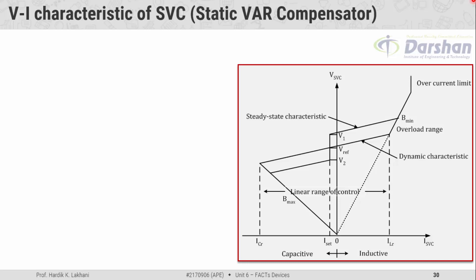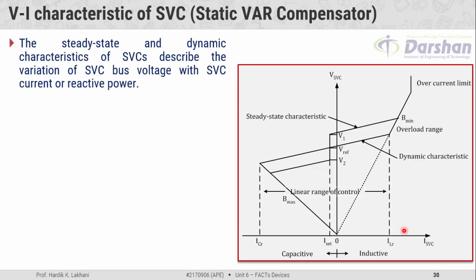This is the VI characteristic of the volt ampere reactive compensator. On the x-axis, the parameter is the current through the SVC, and on the y-axis the parameter is the voltage. The steady state and dynamic characteristic of SVCs describe the variation of SVC bus voltage with SVC current or reactive power, giving us information about the variation of voltage across the shunt connected FACTS controller over the variation of current through it.